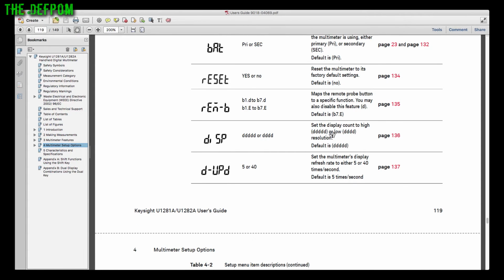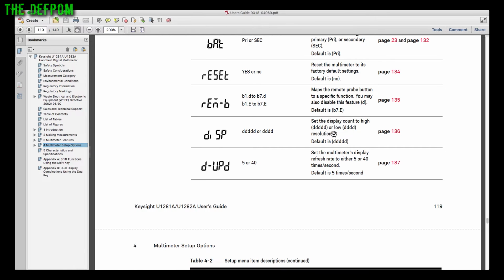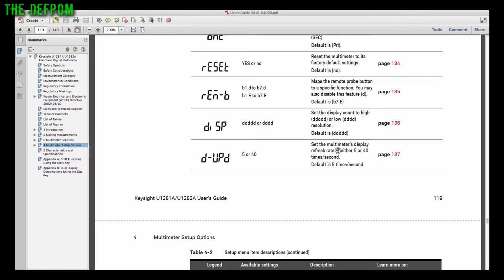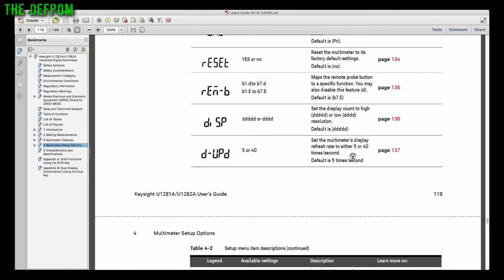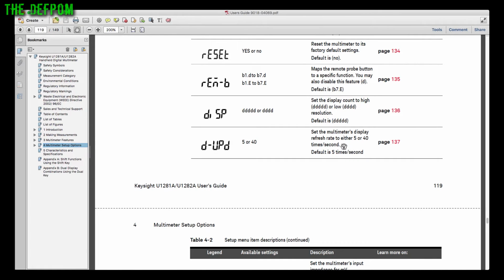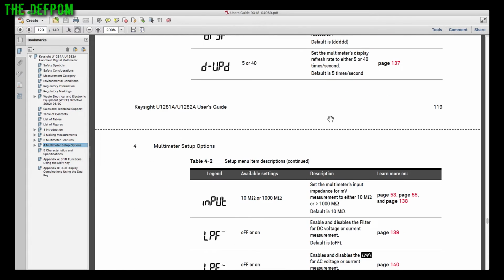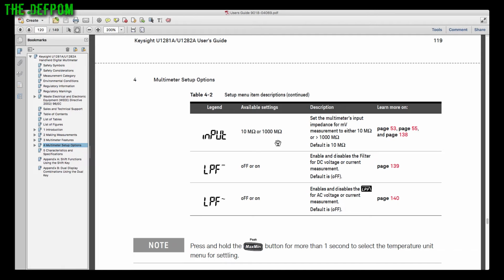Display count, so you've got high resolution and low resolution, which means you can get faster readings if you change it to low resolution. Default is high res, which is 5 digits or 4.5 digits. But you can go to a lower resolution, which gives you faster readings. You've also got the same thing here, multimeter display refresh rate, 5 or 40 times a second. I believe if you've got it set to 40 times a second, it automatically drops down to the lower resolution. I haven't tried that. And other settings here on the next page. Input impedance. In the millivolt range, you can have either 10 meg or basically 1 gig of input impedance. Some other multimeters actually do this, like my Siglent bench multimeter.